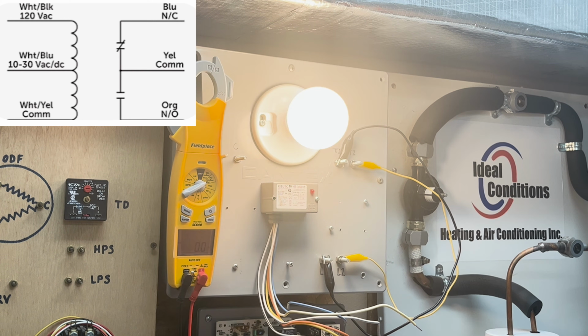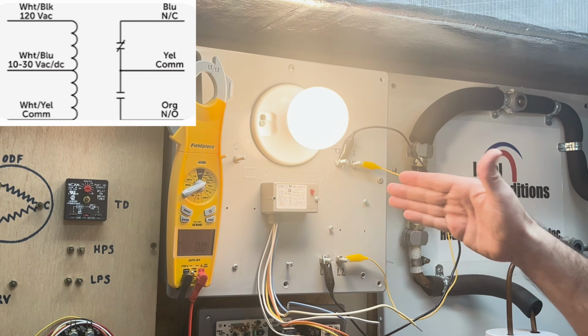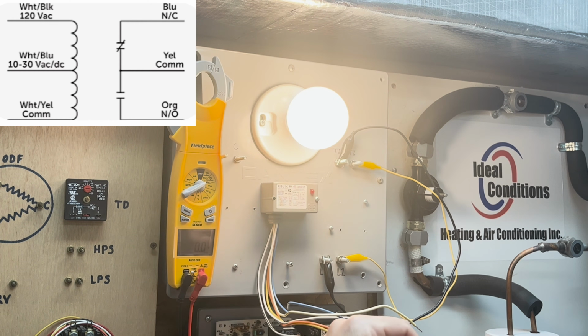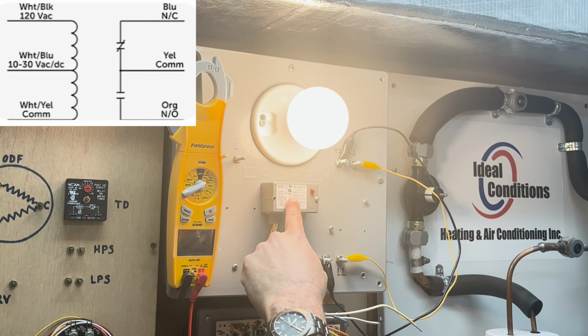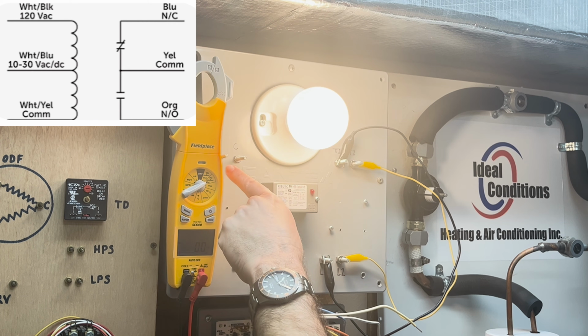Now our next goal is to wire this up to the relay. There's a couple of terminals that are for coil, and there's a couple of terminals that are for the contacts. There's a label on the relay that shows you that you can use common on the 24 volt side, common on the DC side. When I say 24 volts, I'm referring to volts alternating current. DC volts between 10 and 30, DC volts direct current, or 120 volts alternating current. I don't have a neutral up here, so I can't demonstrate the 120, but I can show you the volts alternating current between 10 and 30 volts because we have 27 volts between R and C.